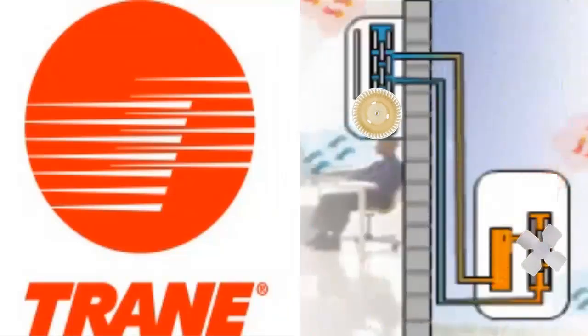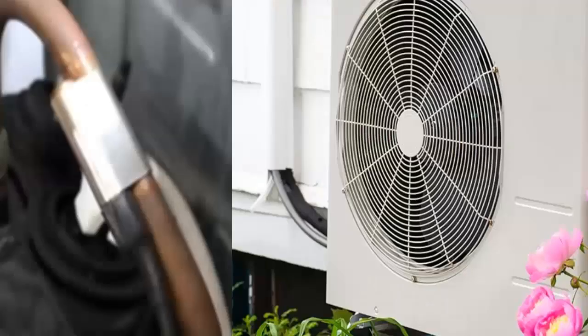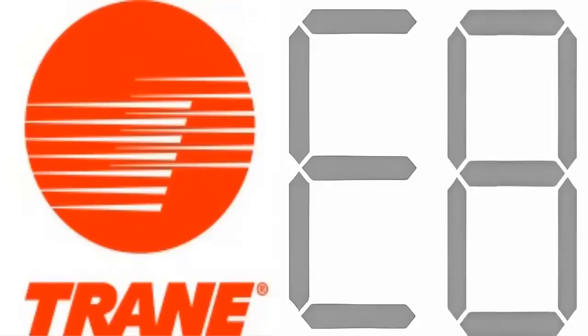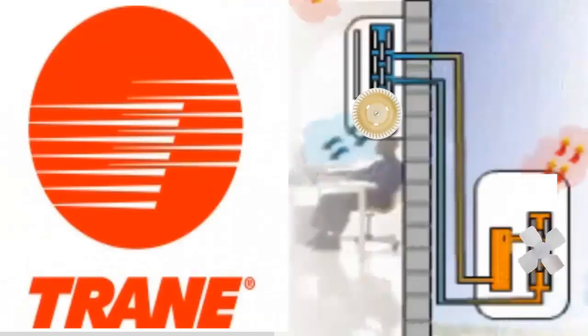5. When there are issues with the temperature sensor located in the outdoor unit, which measures the temperature of the refrigerant gas leaving the compressor, codes E8 and F5 can be generated.